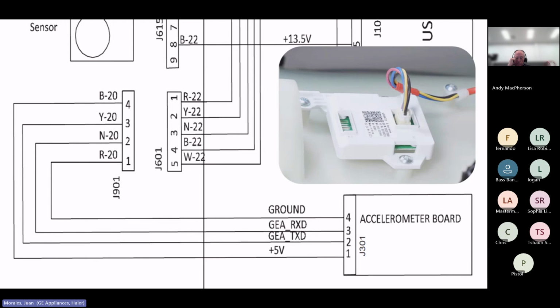The lines we're going to check are ground and 5 volts, which in both cases happen to be pins 1 and 4, whether you're at the main or at the accelerometer. Because the accelerometer is at the top of the machine, you can remove the cover and check voltage at the main and at the accelerometer to make sure the wire harness is good. If you're not getting voltage from the main control board to the accelerometer, that's an indication you have to replace the main board.